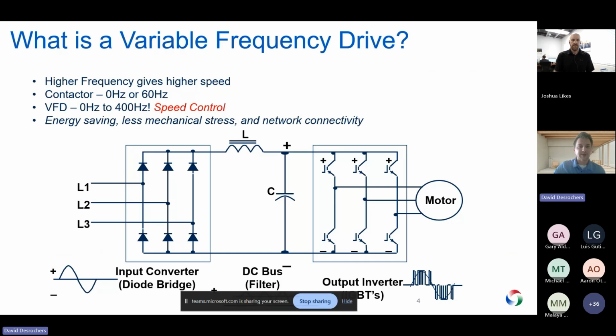The first thing I want to throw in, it's always nice to start with basics. So what is a variable frequency drive? Higher frequency is going to give you a higher speed. Just like when you run a motor across the line at 60 hertz, typically with a contactor, you'd only get 0 or 60 hertz. You don't get anything in between. The variable frequency drive allows you to get every conceivable frequency, down to 100th of a hertz, in between that range. And the Yaskawa drives can do up to around 400 hertz and above on some models. That's giving you full speed control for whatever application you might be using it for.